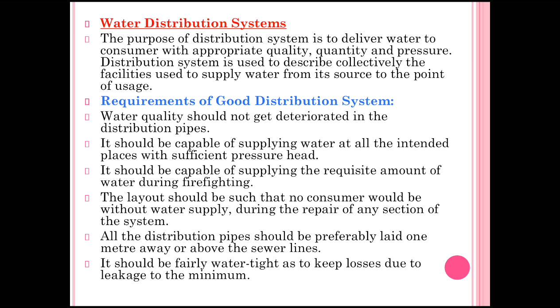The next concept is the water distribution system, which is the last part of this chapter. The purpose of the distribution system is to deliver water to consumers with appropriate quality, quantity, and pressure. A distribution system collectively describes the facilities used to supply water from its source to the point of use. The requirements of a good distribution system are: water quality should not deteriorate in distribution pipes; it should be capable of supplying water at all intended places with sufficient pressure head; it should be capable of supplying the required amount of water during fire fighting; and the layout should be such that no consumer is without water supply during repair of any section.